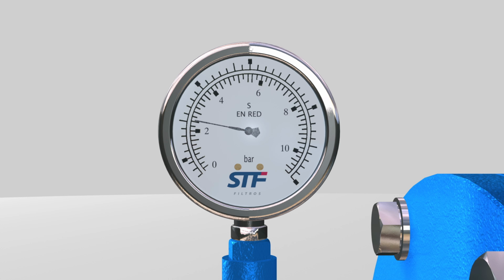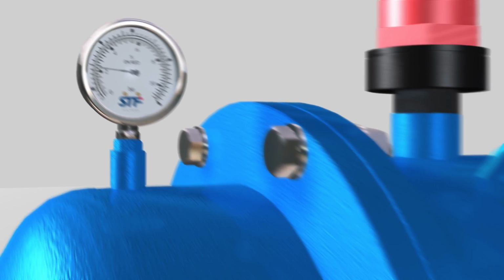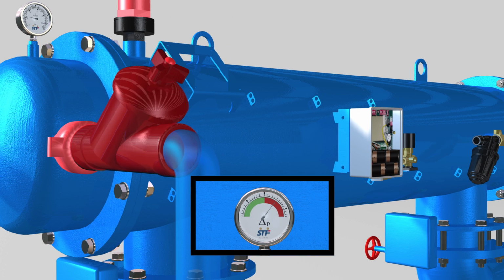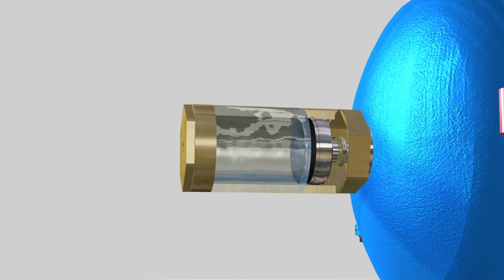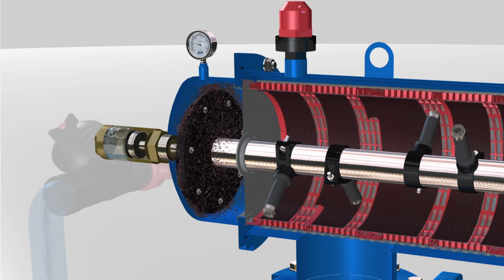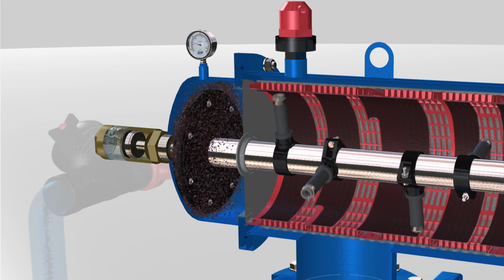Particle accumulation generates a pressure differential between the two sides of the screen. Once the preset value is reached, the backwash process starts. When this value is reached, the DP acts on the control board, which orders the drainage valve housed in the backwashing chamber to open and the hydraulic piston to void, which enables the lengthwise movement of the scanner.